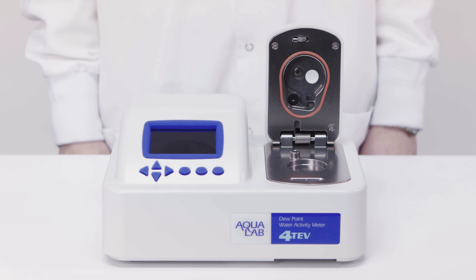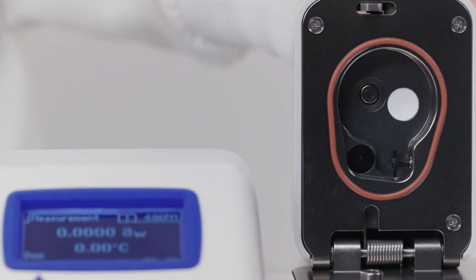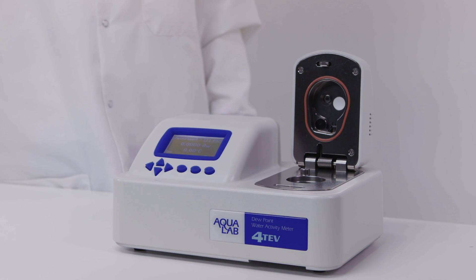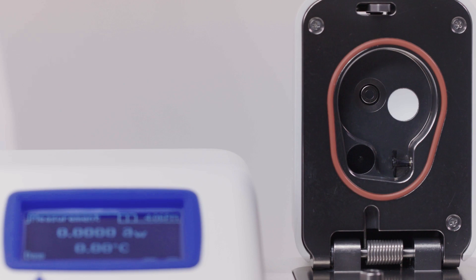The Series 4 TEV can handle volatiles too, but it is for people who only occasionally need a volatile sensor. The Series 4 TEV features a capacitance sensor alongside the chilled mirror sensor. The capacitance sensor is a secondary measurement method. It's good enough for many situations, but not on the same level as the dew point and tunable diode laser sensors. The Series 4 TEV lets you choose the sensor you want, using the higher accuracy dew point sensor most of the time, and the capacitance sensor for samples that have volatiles in them.